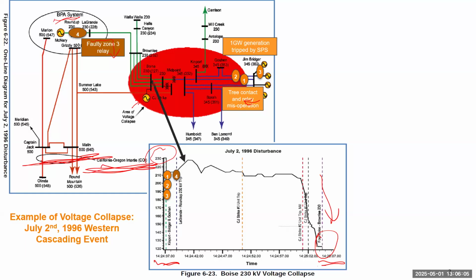Usually on each transmission line there is protection. The protection tries to calculate the apparent impedance based on the local voltage divided by the local current. If you have a short circuit on that line, the voltage divided by the local current can be very small, so you know there's a short circuit. But sometimes the voltage divided by current is not that small, and there's a possibility the short circuit is not on this line but on a neighboring line. So you can set up a delay time, which means that if the measured impedance suddenly drops to a very low value, it trips the line immediately, but if it's not that low, it takes some time. You wait for the protection on that neighboring line to trip, but if that protection fails, you can trip. That's called a zone 2 relay.